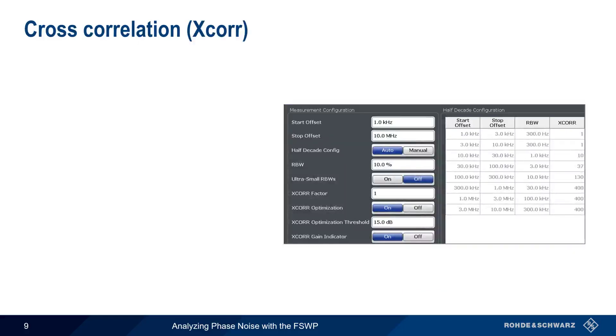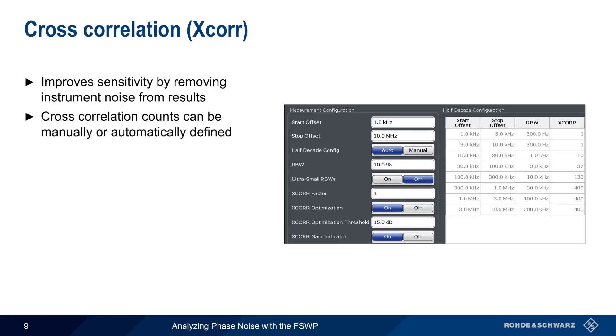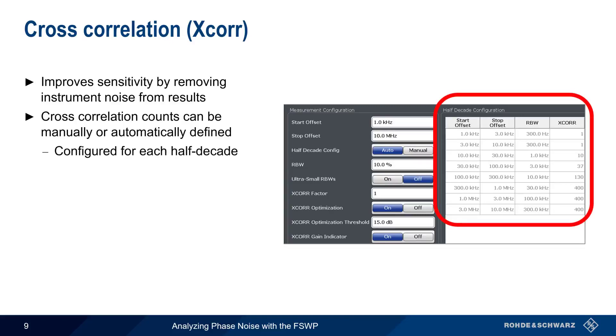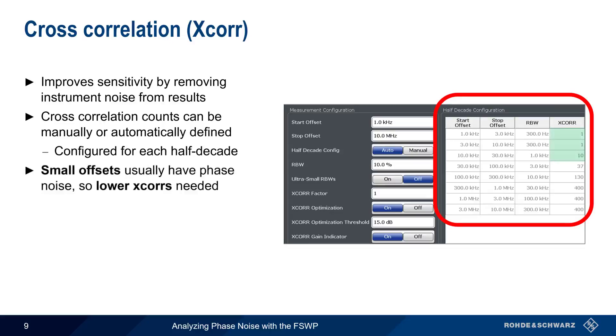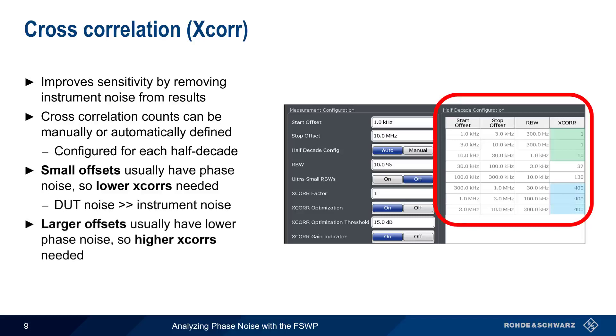The next most important settings are for cross-correlation. Cross-correlation improves sensitivity by removing instrument noise from the phase noise results. The number of cross-correlations can be manually or automatically defined, and are configured for each half decade. Phase noise tends to be higher at smaller offsets, so a lower number of cross-correlations are needed there — the DUT phase noise is much higher than the instrument noise. On the other hand, DUT phase noise is usually lower at larger frequency offsets, so a higher number of cross-correlations are needed to reduce the effects of instrument noise.